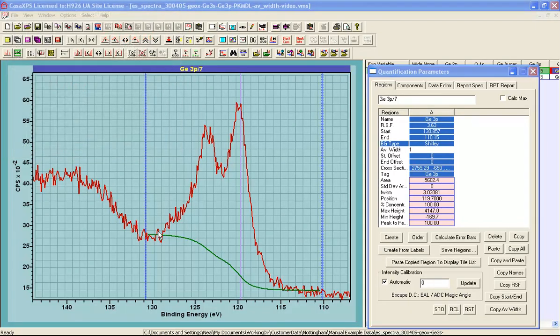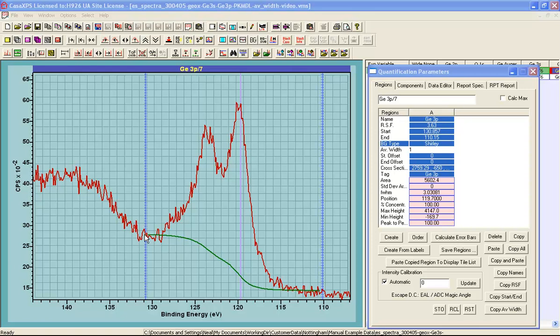The precision with which a peak area is measured can be enhanced if we were to measure these data with improved sensitivity. That is to say the count rate increases if we use a higher pass energy or a wider aperture. The cost of using a higher pass energy and a wider aperture is that the shapes within the peaks are then influenced by the instrument. So there is a balance between the precision and the sensitivity that is appropriate for calculating chemical state information. In this case this is germanium oxide on germanium and we would like to see the ratio of these oxide and elemental peaks for germanium. So increasing sensitivity is not necessarily the best for this type of analysis.